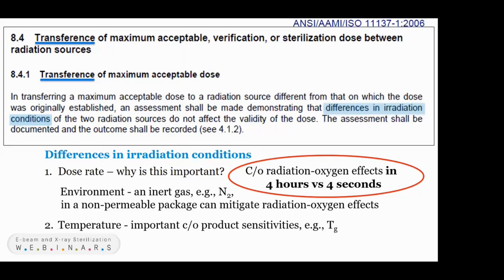And then temperature. So in gamma, you have an elevated temperature for that entire four hours, and in e-beam, depending on your materials, you can have a spike in temperature for a few seconds that will dissipate. So that has to be considered. Is that clinically relevant for your system?